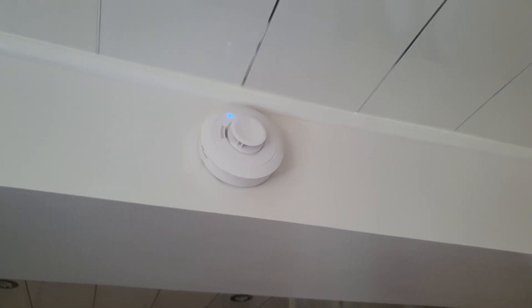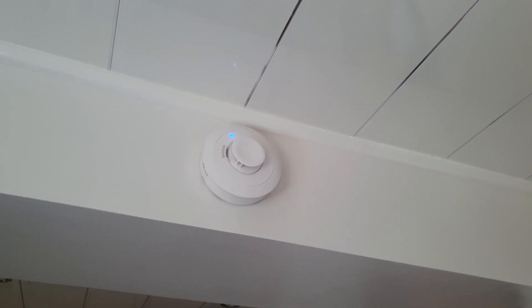We'll set that and go test something else. I'm just going to test this heat detector — I'm just going to use the test button today. I'm going to go silence from upstairs and go around the sounders.